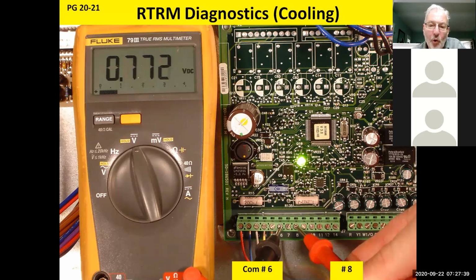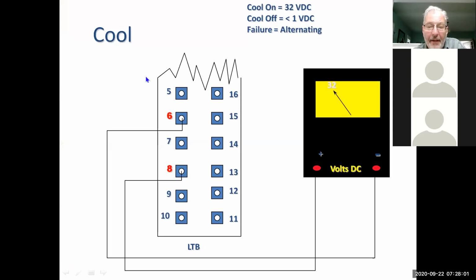Now on the cool diagnostics, so if you go between terminals 6 and 8, we have cool diagnostics available, and it's kind of the same as the heating diagnostics. If it's less than 1 volt DC, that means that we don't have an active call for cooling. Okay. And this is just to show you that it's the same on the old units as the new units. But if I have 28 to 32 volts DC, that means I have an active call for cooling at that point. The unit should be running.